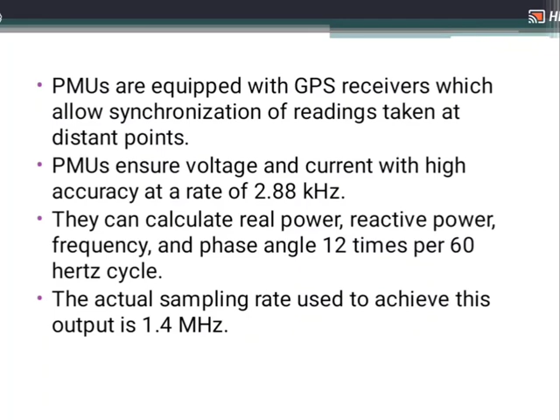So they can calculate the real power, reactive power, frequency, and phase angle around 12 times per 60 hertz cycle, because this is the difference between SCADA and PMU. The speed of capturing the data is very high as compared to SCADA. So the actual sampling rate used to achieve this output is around 1.4 million hertz. So it is a very high frequency device.